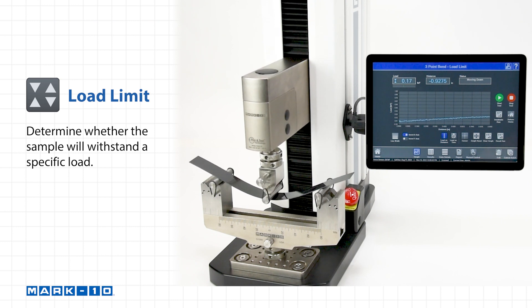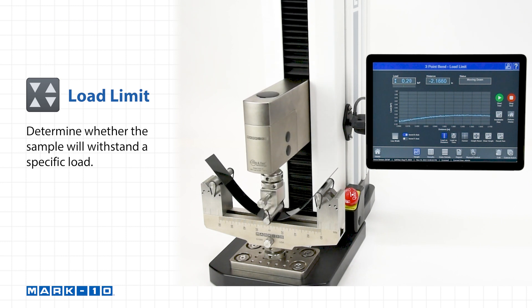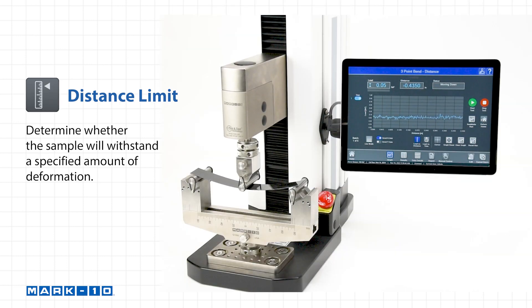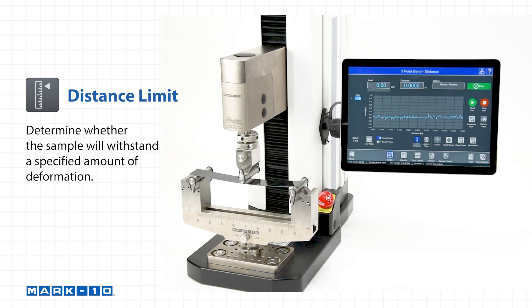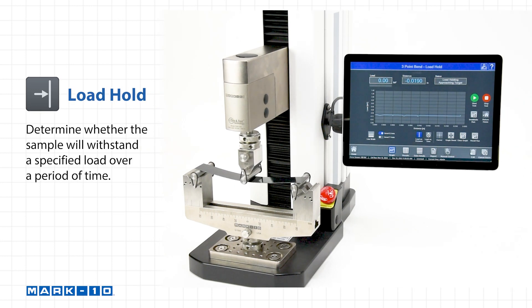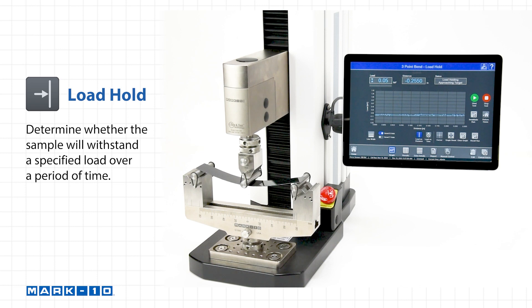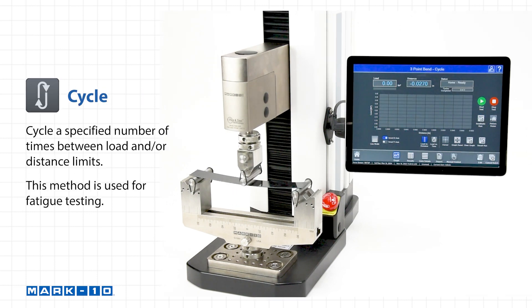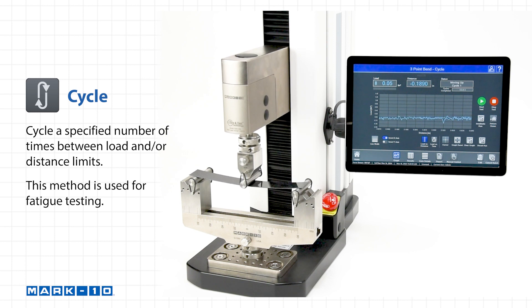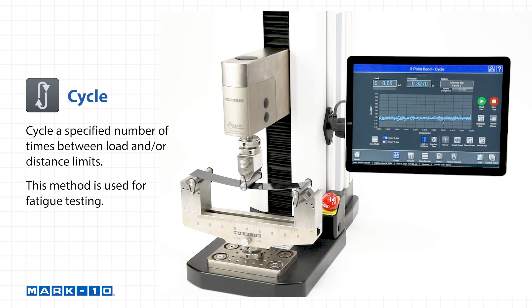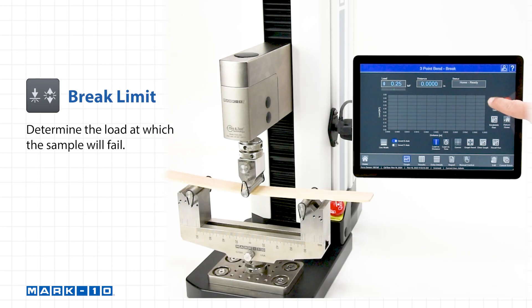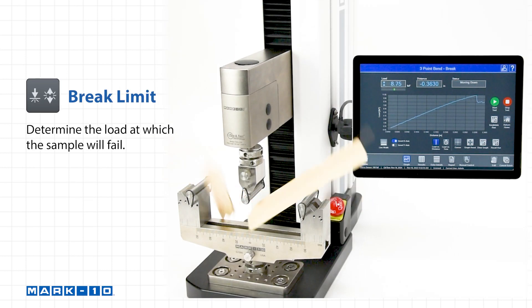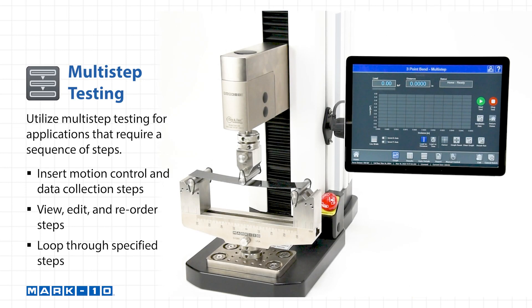Load limit determines whether the sample will withstand a specific load. Distance limit determines whether the sample will withstand a specified amount of deformation. Load hold determines whether the sample will withstand a specified load over a period of time. The cycle test cycles a specified number of times between load and/or distance limits — this method is used for fatigue testing. Break limit determines the load at which the sample will fail.